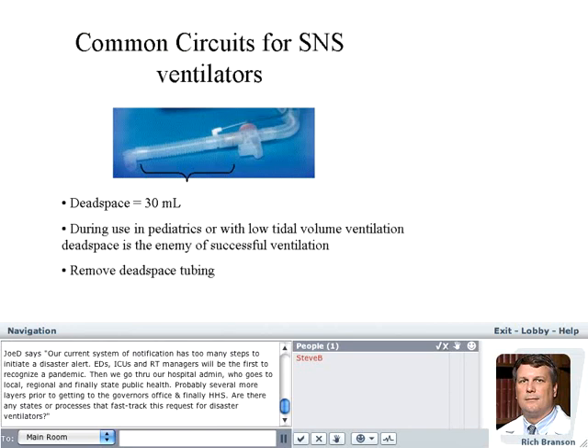But this is the circuit that comes from the Strategic National Stockpile, and you can see that there's that flex tube and elbow that goes to the patient connection, the endotracheal tube. It adds about 30 milliliters of dead space, which is going to be no big deal in your adult patients, but in pediatrics it is going to be a problem, and you should be aware of that and be ready to remove that and use another adapter to connect directly to the endotracheal tube to remove that dead space. It will be a real problem for controlling CO2 when you start getting to low tidal volumes, those less than about 200 milliliters. Again, that will be for either ventilator.